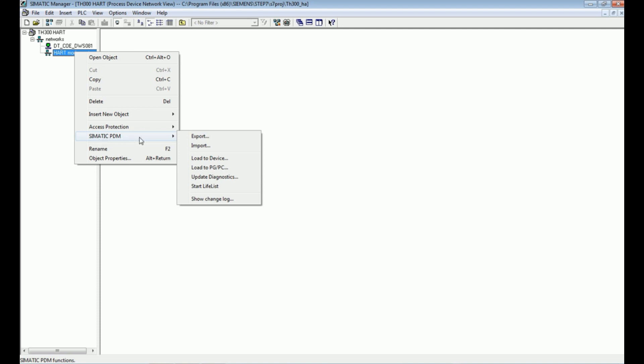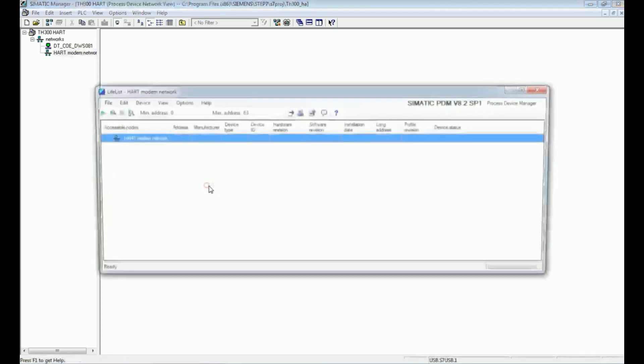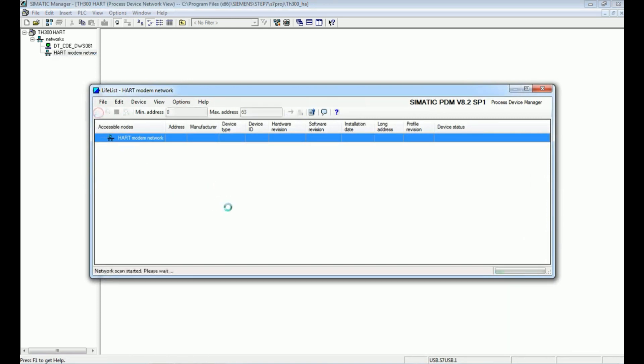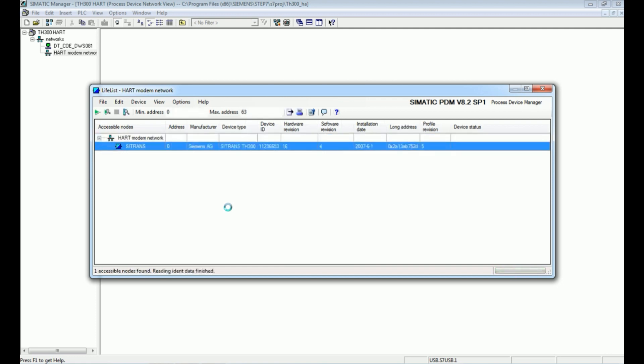In the HART modem network we will track the device. For that we will switch to SIMATIC PDM and start the live list. This live list will scan the whole network via the HART modem, and the device connected to the HART modem will be shown here. We will get the address, manufacturer, device type, device ID, hardware version, and software version from this live list, and based on those details we will select the object.